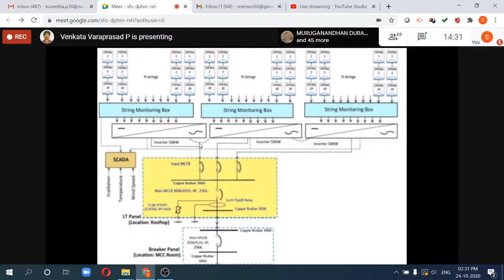From the inverter, whatever AC power is there is connected to the breaker, and from that breaker it is connected to the common busbar point. From this busbar point, you can take a protecting device. One is a relay, and it is also connected to the surge arrestor. From that protecting device, again we connect to one busbar. So if any failure occurs, then we can simply isolate this point and work on it. For that purpose, we need to provide a breaker. After this copper bus bar, it is again connected to the distribution side, the LT panel.